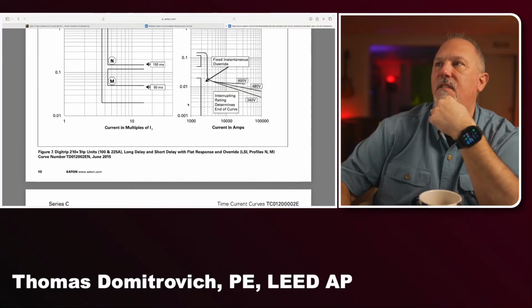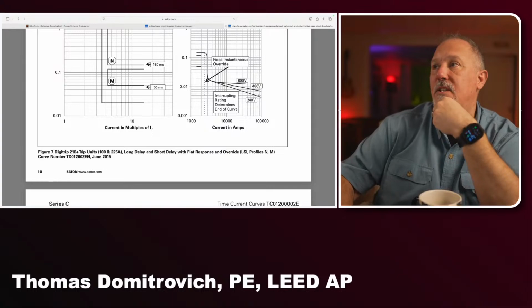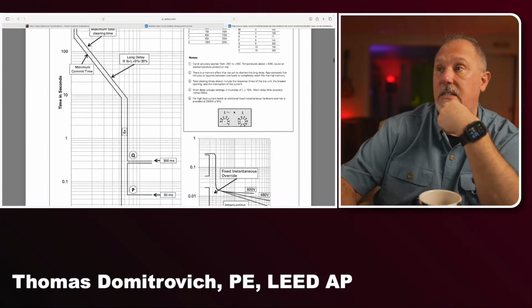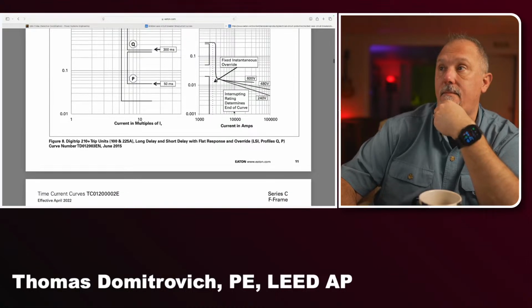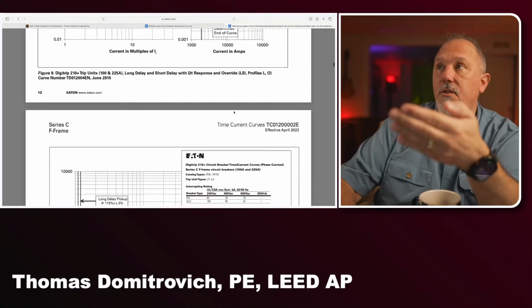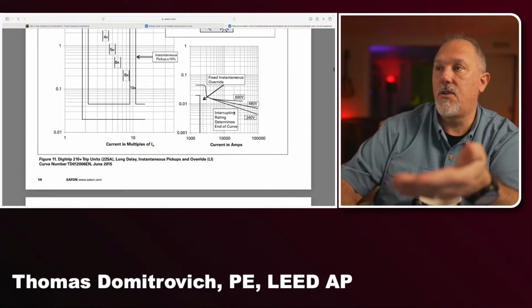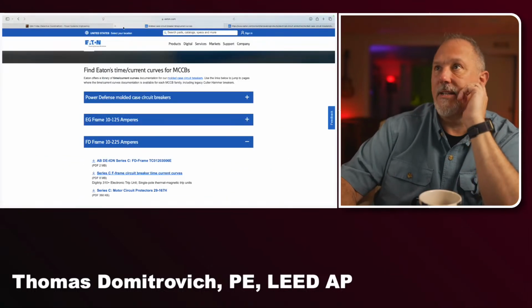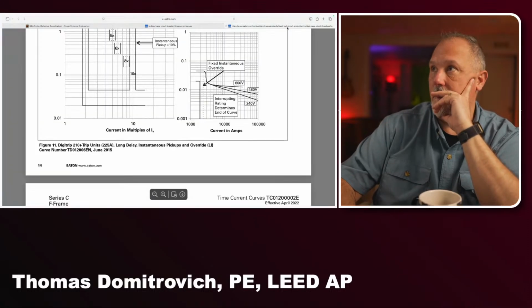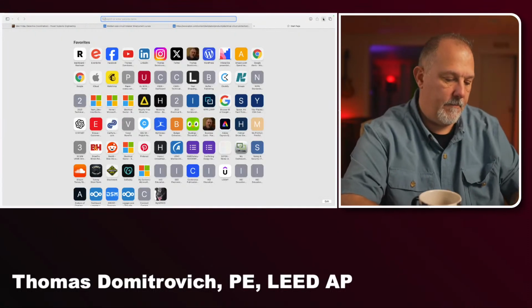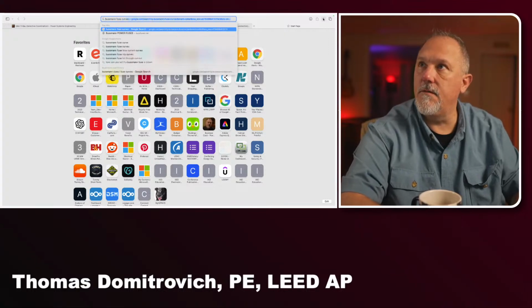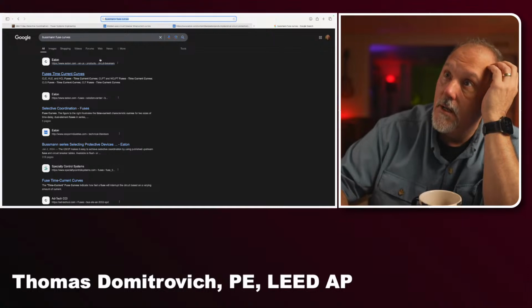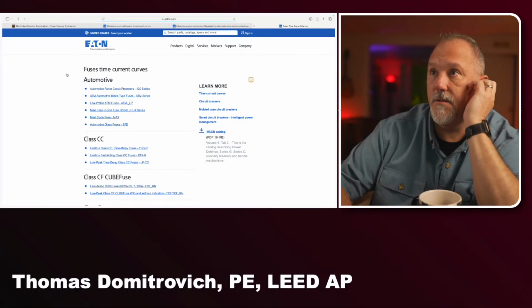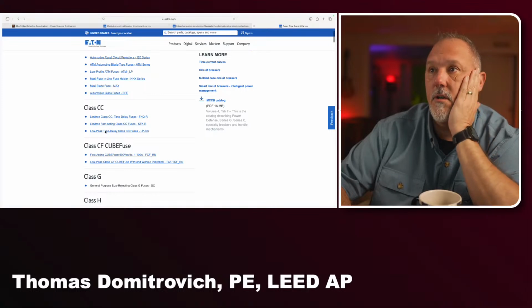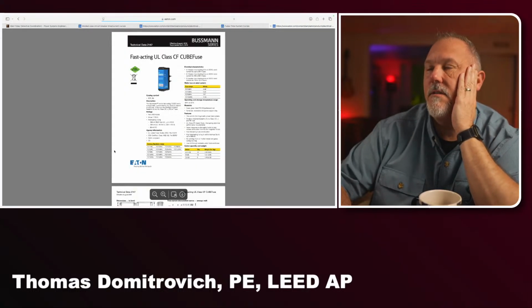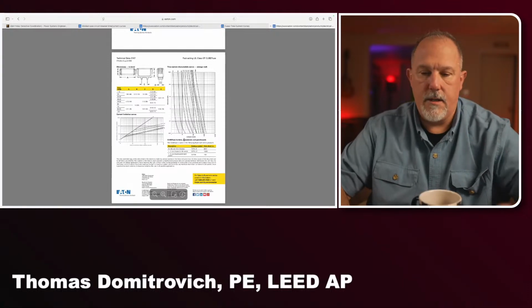There's 0.001 for the instantaneous region, and we show what happens below 0.01 seconds on our TCC curves. So we do provide data down to 0.001. I was going to say, no, we don't. What about fuses? Bussmann fuse curves. Fuse time current characteristic curves. Here's your class, there's your fast acting, here's your CF fuse. Let's see what they do here.